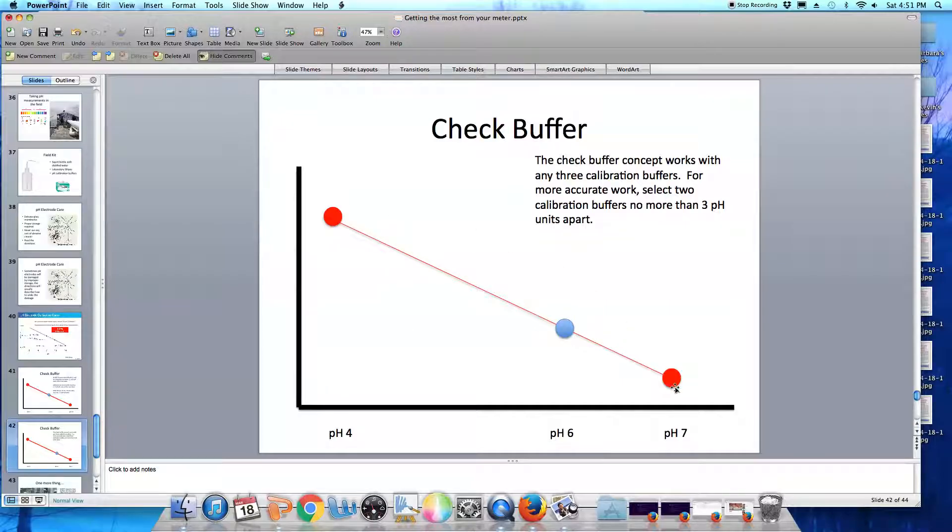In this example, we calibrated at pH 4 and at pH 7 with our check buffer, which is read as if it were a sample, at pH 6. If you check the New Jersey Administrative Code, it will describe some situations where your pH probes must be calibrated with two buffers no more than 3 pH units apart. The important thing to remember is that the fewer pH units between your calibration buffers, the more accurate your pH readings are going to be.